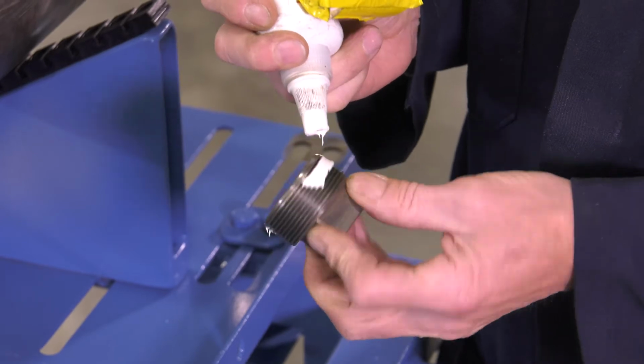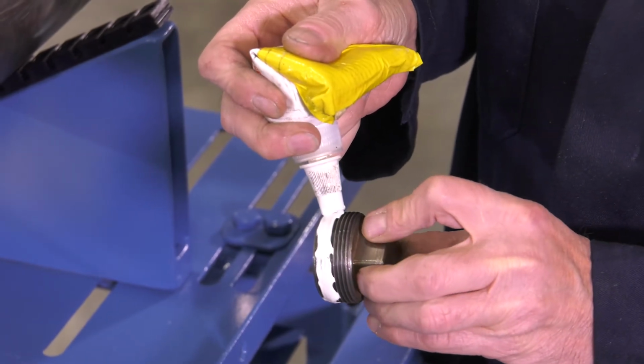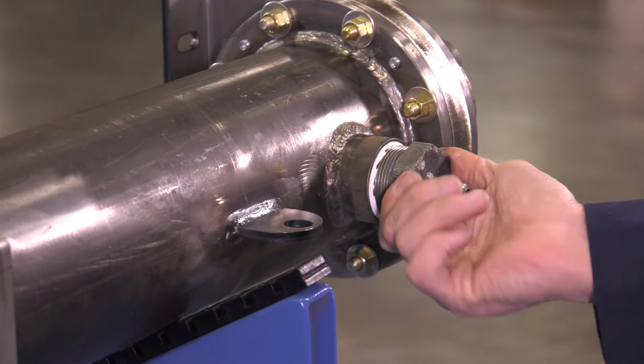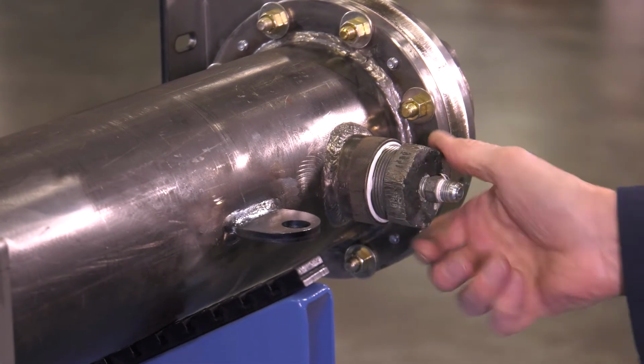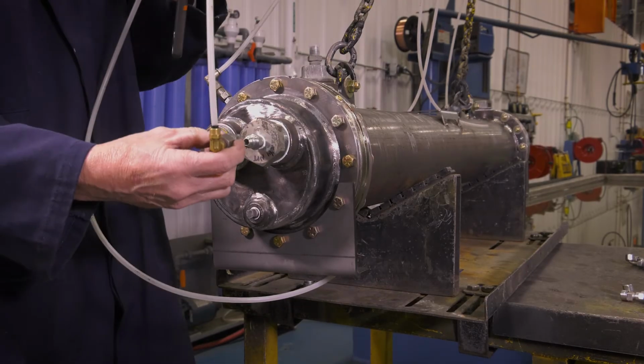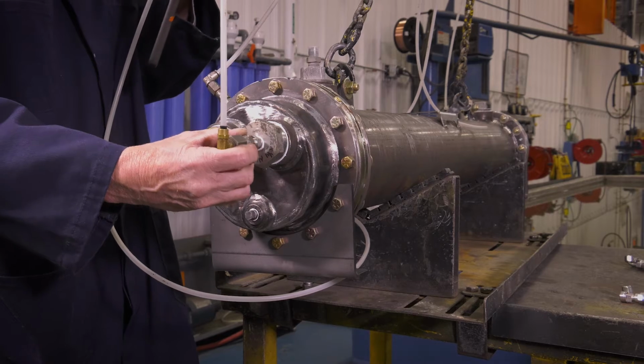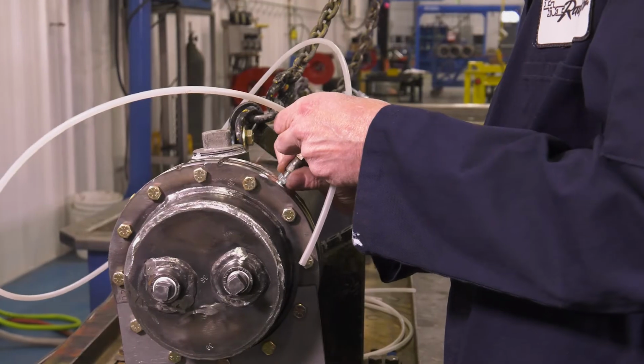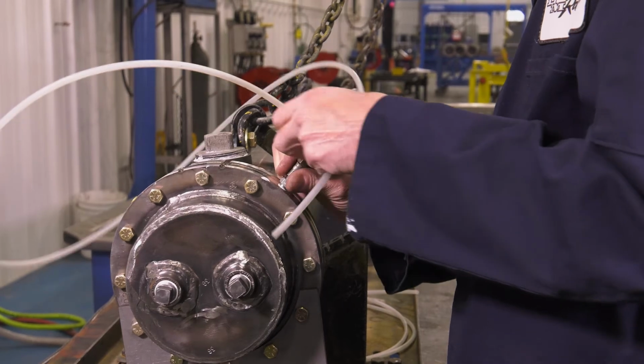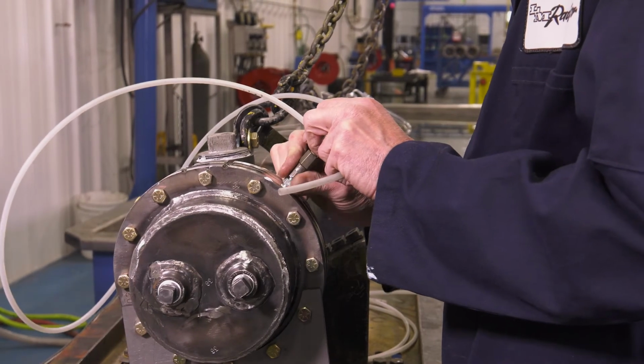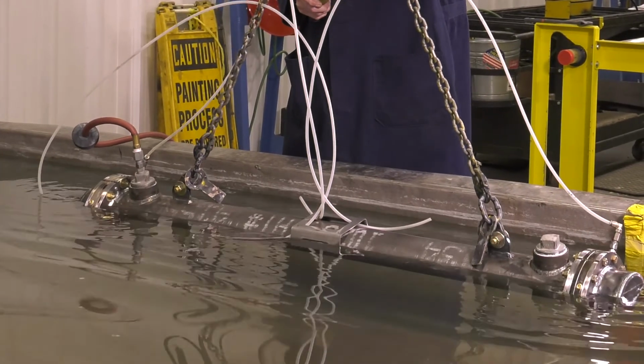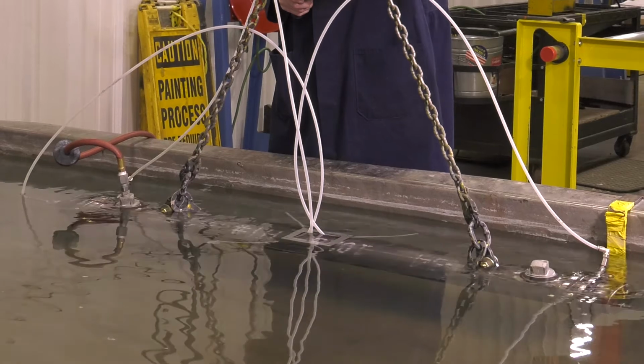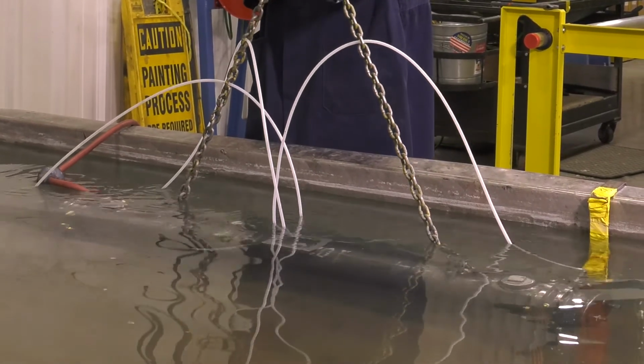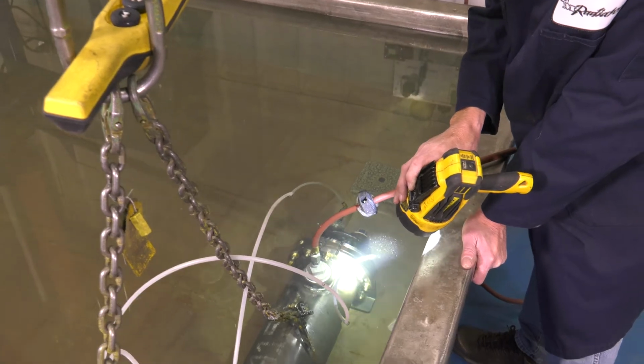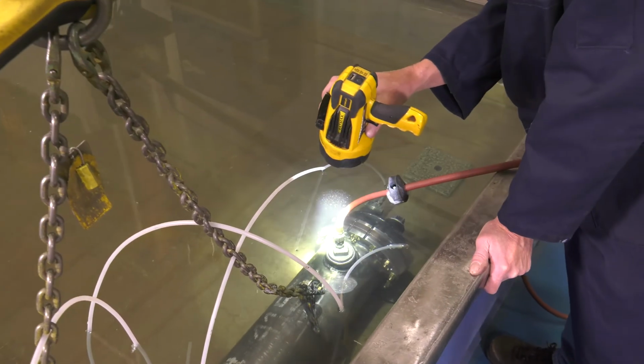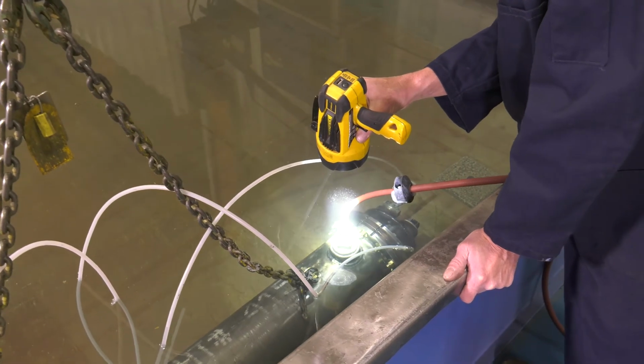Plug off all ports in preparation for pressure testing the cooler for leaks. Leave one detection port in each header open for testing. To test the shell side, typically the oil side, follow the pressure cycle steps in the System Protector Service Manual. Only use fittings appropriate for the test procedure and apply pressure slowly. With the cooler underwater and after residual bubbles are gone, begin the test sequence. Check for leaks at the detection ports and tube ends. If a leak is detected, it should be an inner O-ring seal. Pressure should be released prior to repair.